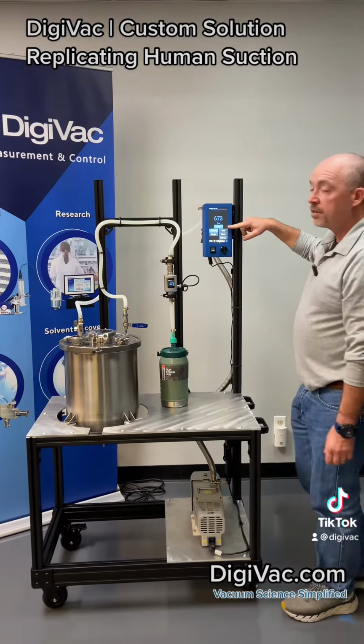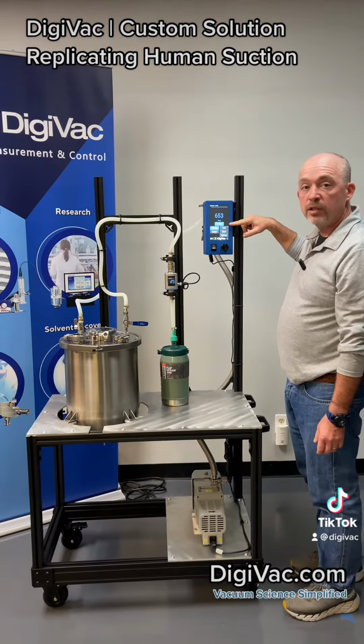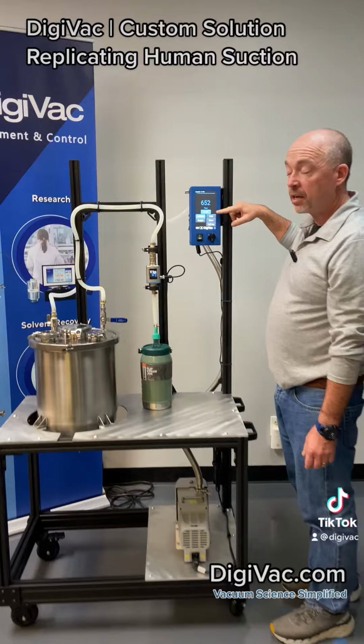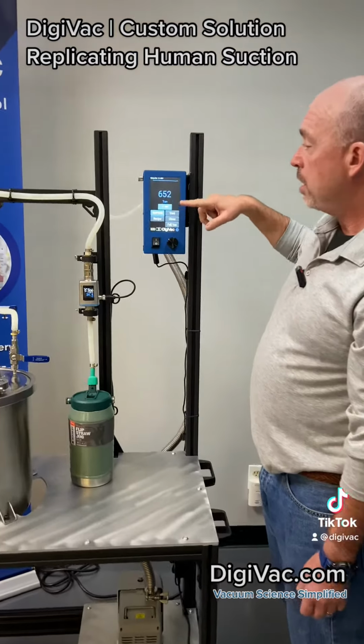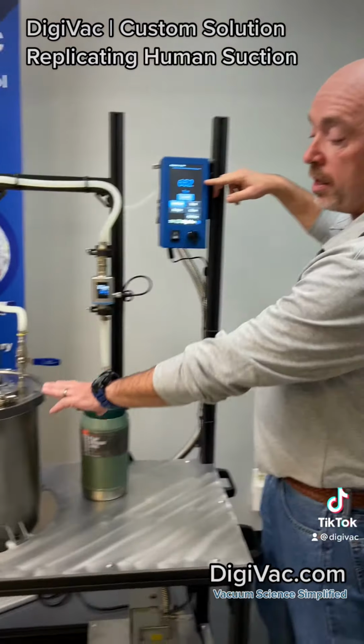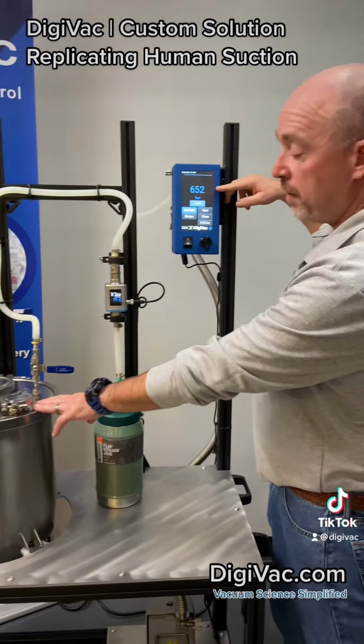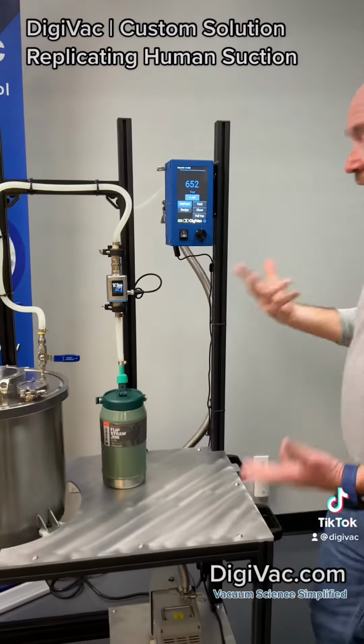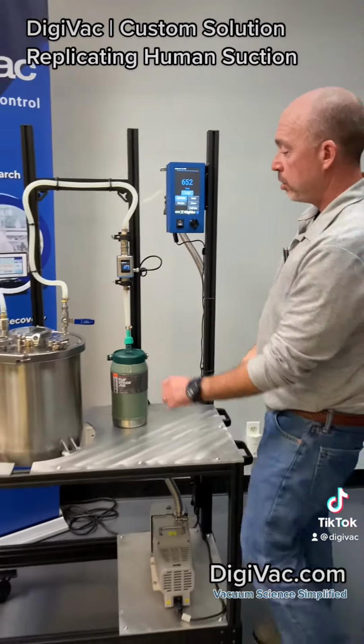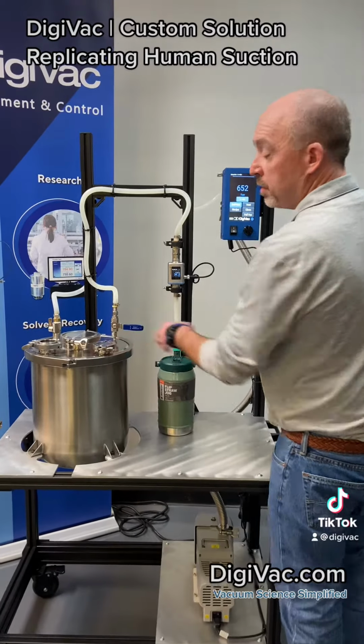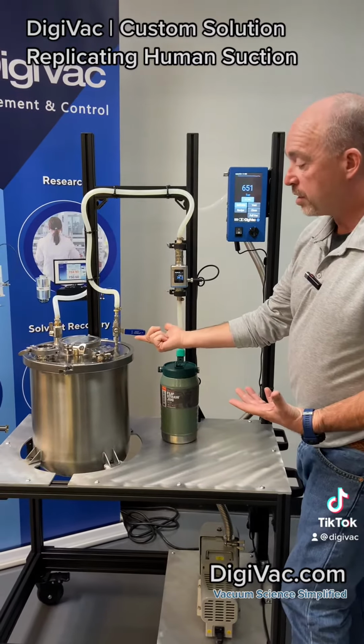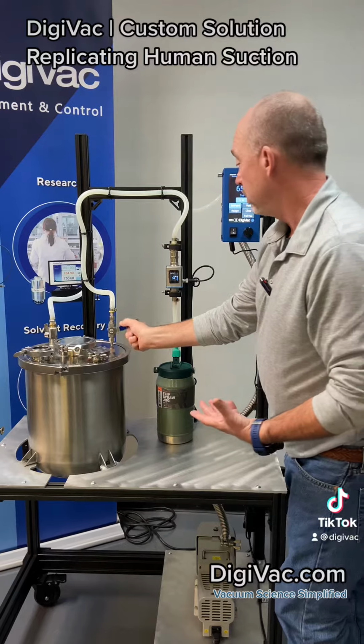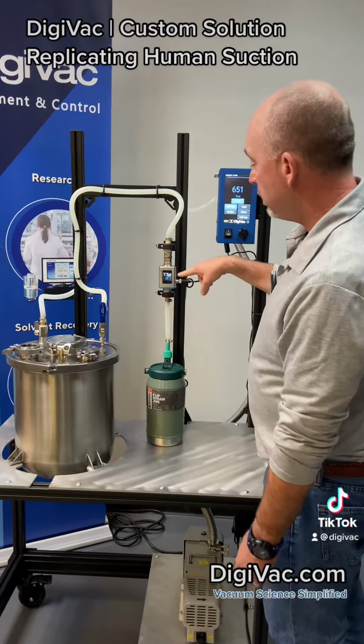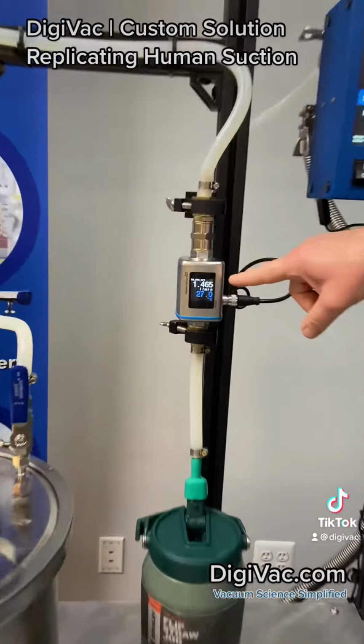We have the set point set at 650 torr, so that's not a lot of sucking pressure, or sucking vacuum. So we see that very quickly this tank is regulated to 650 torr, and now we're ready to do our experiment. So what we'll do is we'll take that breath, which for us is we're actually going to turn this valve on, and then we can see that we're flowing about 1.4 liters per minute.